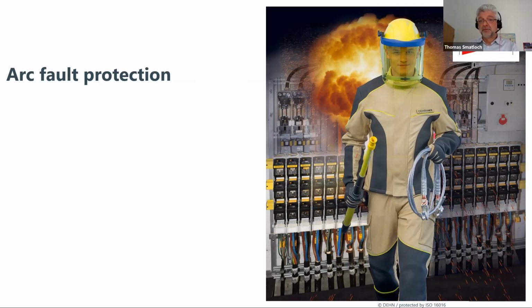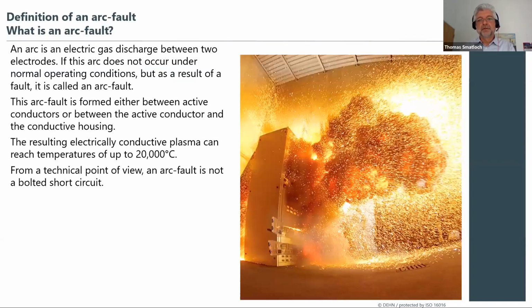An arc fault is a very serious matter, as you probably know. When we look at this actual picture here of a switchgear cabinet nearly exploding due to an arc fault, we should talk about the parameters of such an arc fault. Definition: what is an arc fault? It's an electric gas discharge between 2 electrodes. Electrodes can be parts of the equipment. This can be conductive parts, of course, between parts having voltage and earthed parts, or between 2 phases as well.